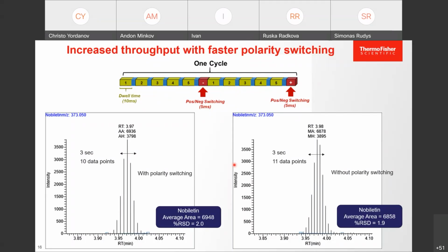When we look at a whole cycle of what the instrument is doing, the green bar represents the dwell time, which means we are measuring our SRM transition. Then the blue represents the switch from one transition to another. Then we do a couple of transitions, and then we do polarity switching. Then we do transitions in the different polarity, and then we switch polarity back. So the polarity switching time is, of course, included in the whole cycle time.